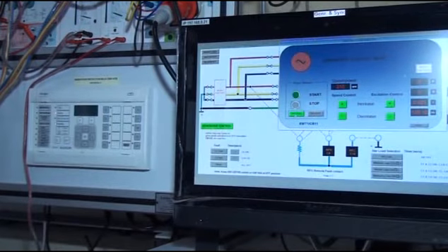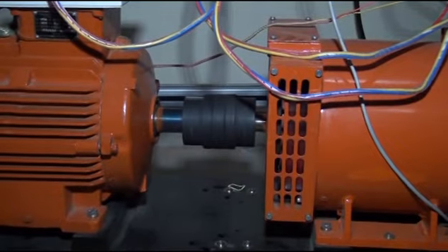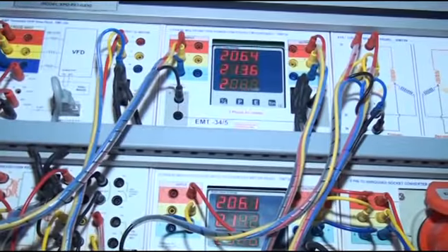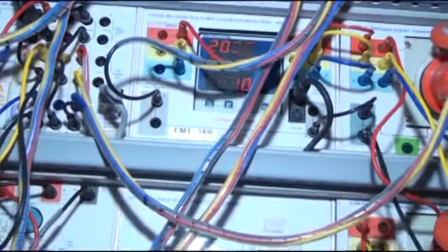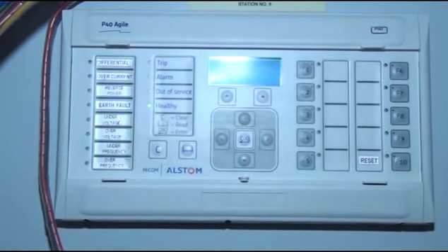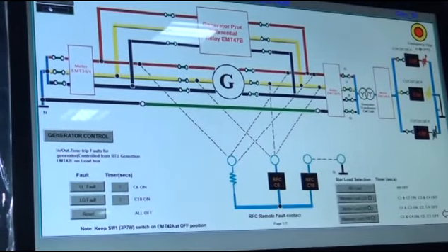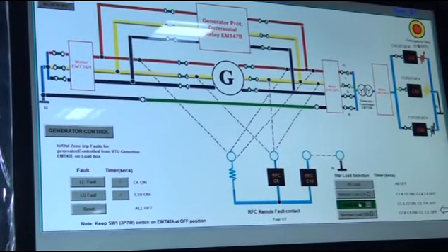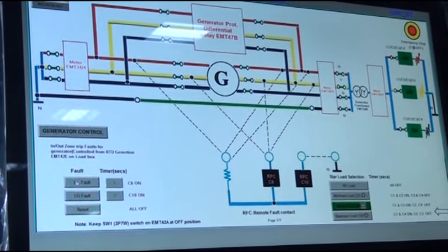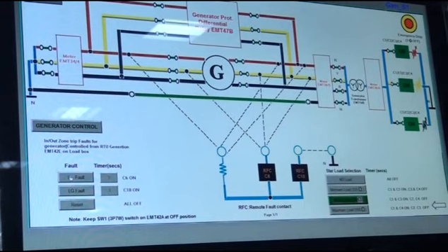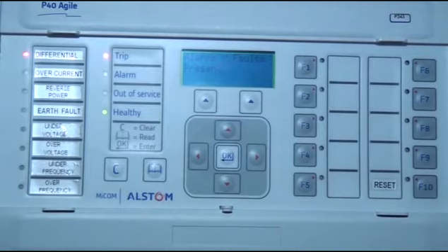Now press the start button on the generator control panel. It will become green. Press the VFD run button and observe that the motor starts rotating. You will get generator voltage at EMT 34 by 5. Observe the relay display; it should not show any alarm or fault. If it shows any fault or alarm, press the relay reset button on the SCADA screen. Now select any load to create a differential fault at the generator. Press the LL fault button on the SCADA screen with timing of 3 seconds. The relay front panel shows the differential fault LED glowing. On the SCADA screen the generation differential protection relay trip message is displayed and the motor stops immediately.